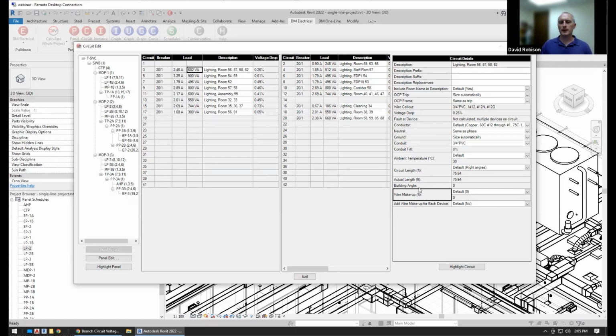There are a couple other options here for circuit lengths. For the right angles, we have the angle of the building, whether it's actually X and Y, or if it's kind of off, rotated. If you're using your default, we're going to use the default building angle. If you specify that we're calculating based on right angles, you can actually change the angle of the building for this circuit. So if we want to use a 45 degree offset, we could change that, and we'll get a different length wire as well.